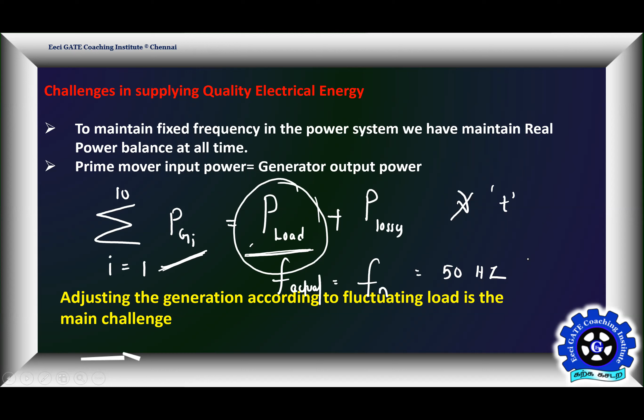Next. So that is the difficulty in fixing the frequency. Now, to fix the voltage to their nominal values, that means to fix the voltages at all points in the power system network to equal to their nominal voltages, we have to maintain reactive power balance in the power system all the time. That means again, the reactive power generated in the power system network should be equal to the total reactive power demanded by all the loads put together and total reactive power loss in the transmission.